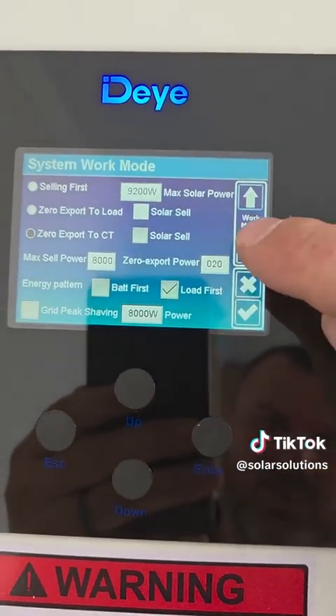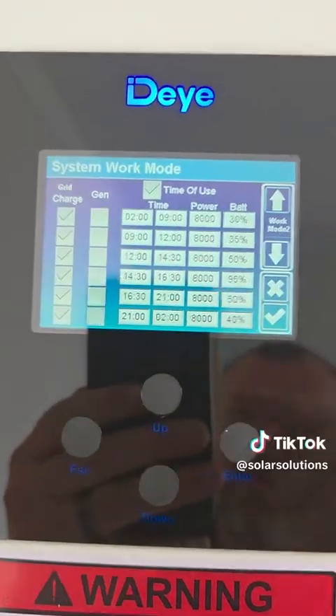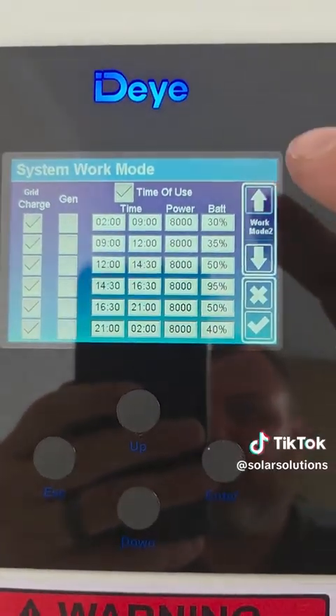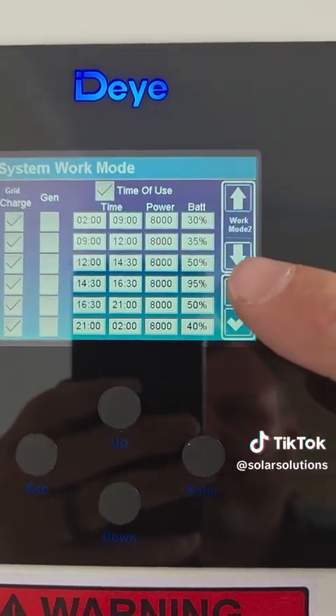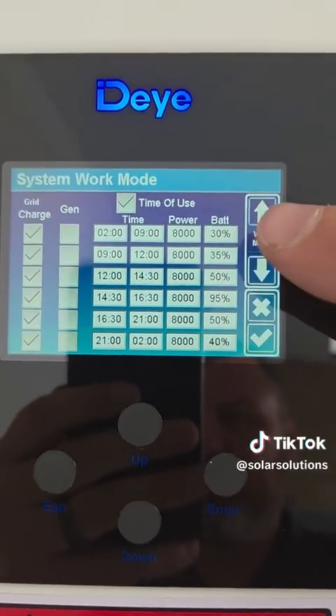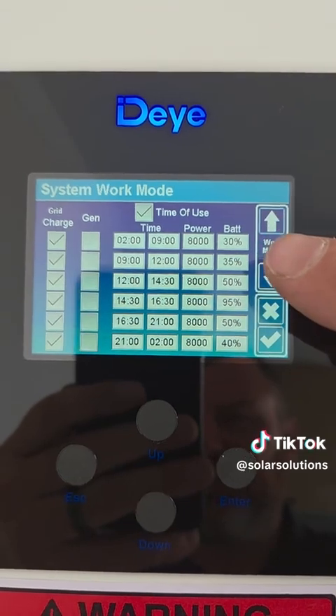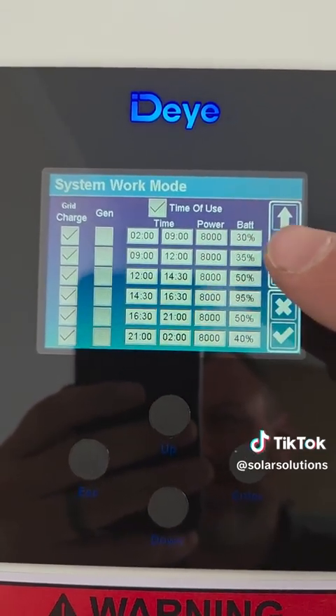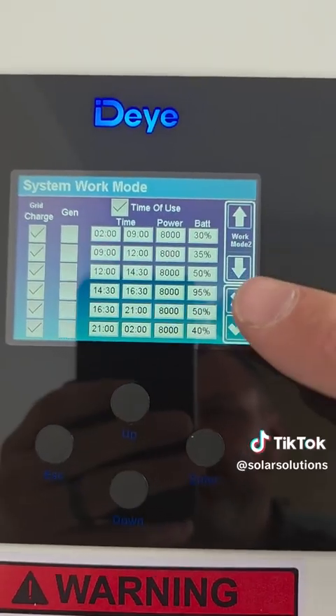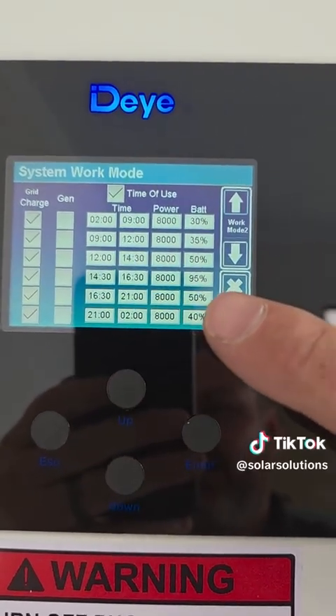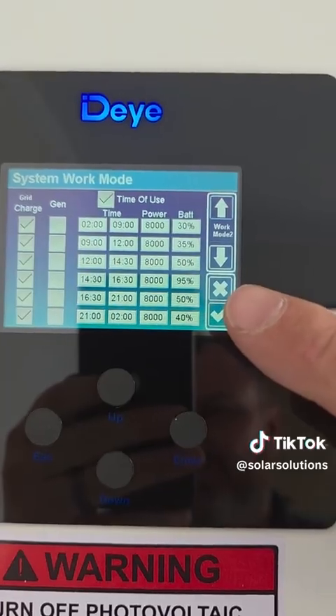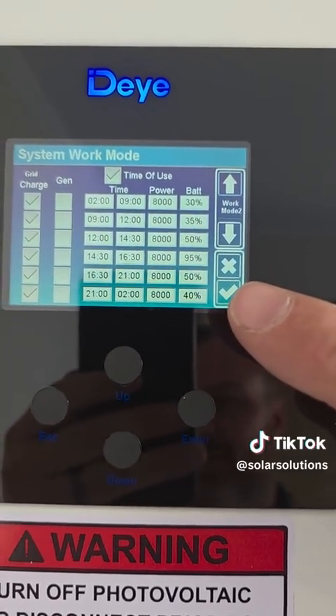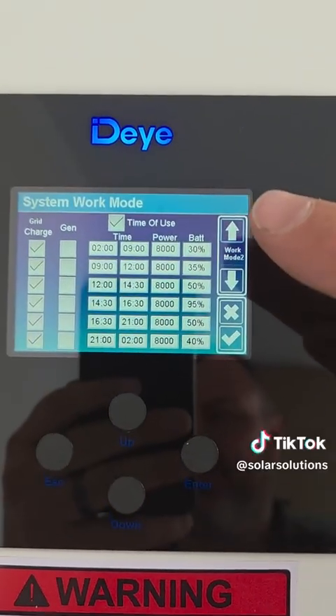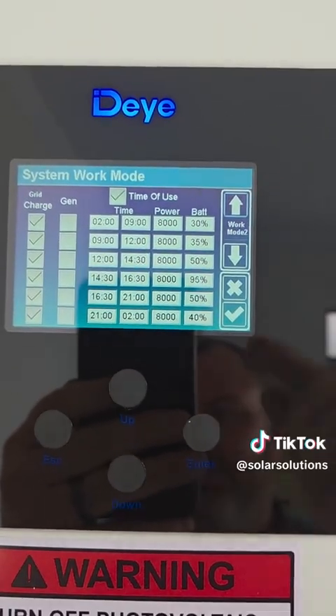Then on your system mode work settings, this is normally what I set for the first time. You can see here the whole purpose is to charge the full during the day, so I make my top charge 95%, and then we're going to discharge every night to 30%. And then the settings in between is just giving the sun a head start to 9 o'clock to get to 35%, 12 o'clock to 50%, and then at 4:30 we start discharging down to 50% again. Then another 10% from 9 to 2 o'clock, and another 10% between 2 and 9 o'clock in the evening.